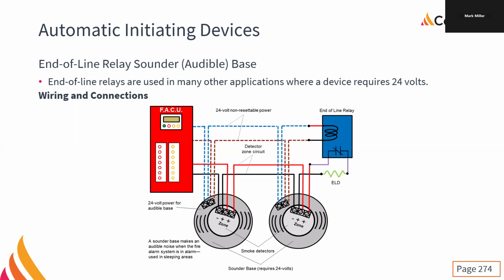Useful in condominiums, apartments, stuff like that, because you can drastically reduce the cost, and especially the maintenance cost, by combining the two together. Right? We're not required, Group R occupancy, we're not required to have a smoke detector in the apartment. We are required to have a smoke alarm by the building code. But if we put in smoke detectors with sounder bases, that covers the smoke alarm requirement, and it lets us know if there's a smoke situation inside the unit. So yeah, it gives us an overall safer environment. So we use sounder bases.